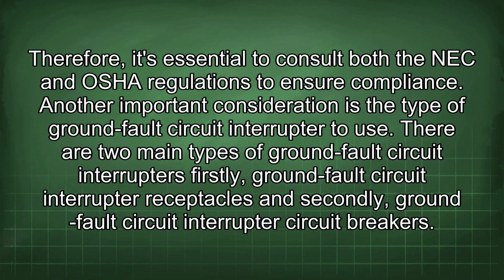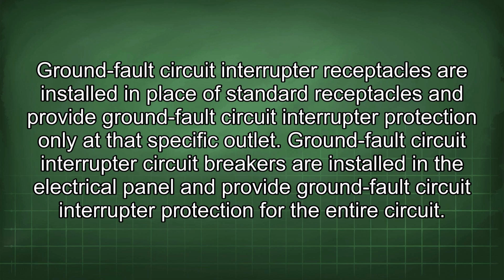Another important consideration is the type of ground fault circuit interrupter to use. There are two main types of ground fault circuit interrupters. Firstly, ground fault circuit interrupter receptacles, and secondly, ground fault circuit interrupter circuit breakers. Ground fault circuit interrupter receptacles are installed in place of standard receptacles and provide ground fault circuit interrupter protection only at that specific outlet. Ground fault circuit interrupter circuit breakers are installed in the electrical panel and provide ground fault circuit interrupter protection for the entire circuit.